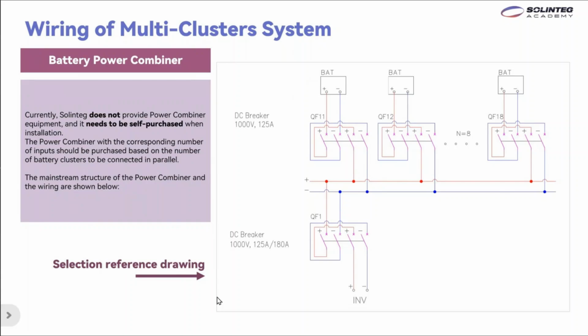We provide a selection reference to help choose the DC breakers. Near the battery, use DC breakers rated at 1000 volt and 125 ampere. For breakers near the inverters, we suggest using 1000 volt with 125 ampere or 180 ampere.